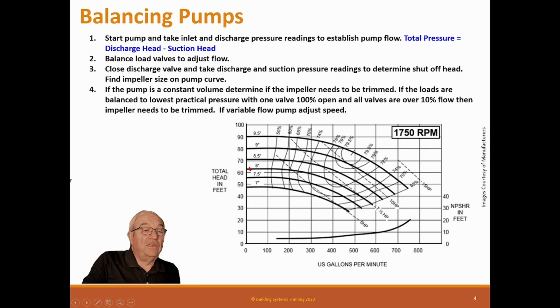Now, why do you need to do that? Well, sometimes pump manufacturers aren't perfect, and what is on the label is not what's in the pump. Because these pumps all come, when they manufacture them, they're manufactured with the largest impeller that pump will handle. And so then to get ready to ship your pump, they have to trim the impeller.